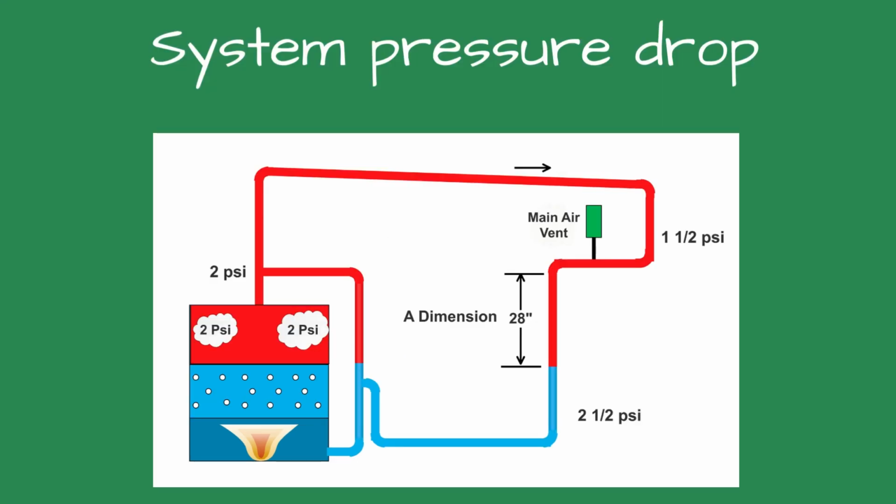While preparing my talk, I sketched a drawing and showed the steam pressure as it traveled through the pipes. Then it hit me. The A dimension is all about weight. It was so clear. When steam leaves a boiler at 2 psi, it loses some of its pressure and becomes condensate. At the end of the steam run, the leftover steam pressure is about 1.5 pounds. How do I get water at 1.5 pounds into a boiler running at 2 psi?